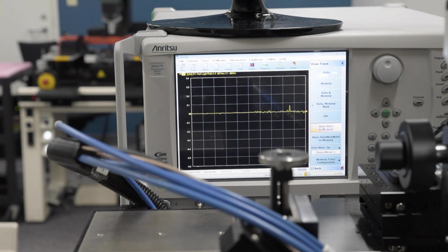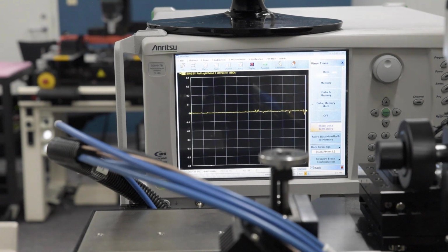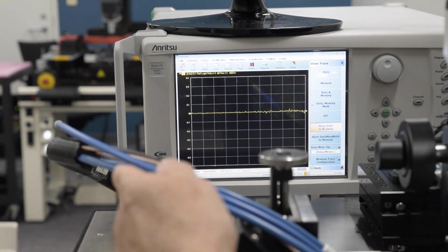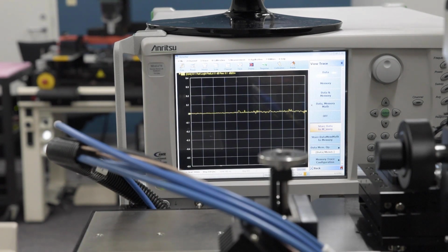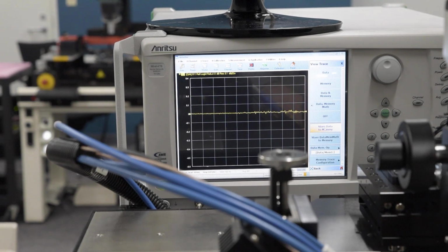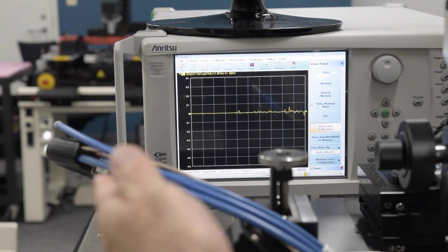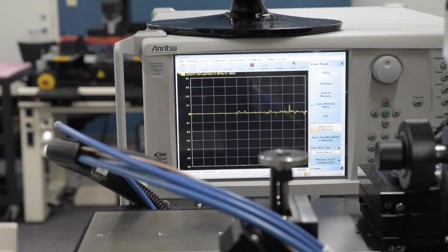But you can see even with a full band, 70 kilohertz to 220 gigahertz, in this system, we are not overly sensitive. That's primarily due to the fact that we have our test and reference receiver down converters located in the module right up at the test port of the module. And so that minimizes quite a bit of any variations you'll get from cable changes or cable flexing.